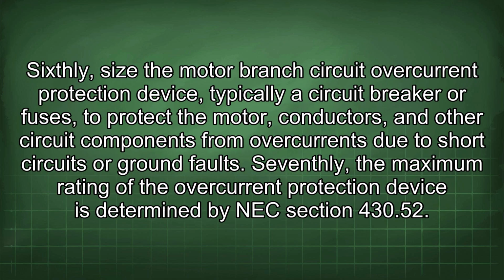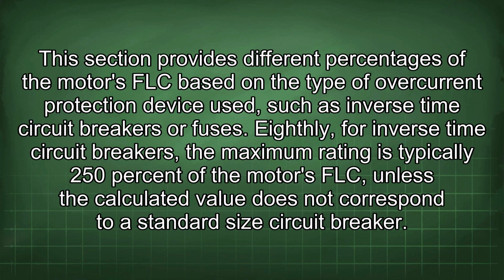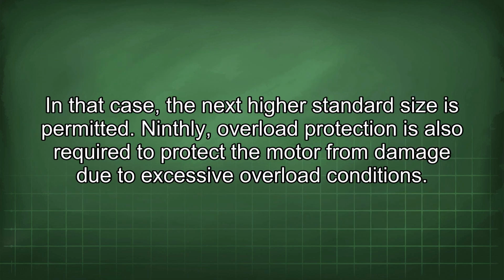Sixthly, size the motor branch circuit overcurrent protection device, typically a circuit breaker or fuses, to protect the motor, conductors, and other circuit components from overcurrents due to short circuits or ground faults. Seventhly, the maximum rating of the overcurrent protection device is determined by NEC section 430.52. This section provides different percentages of the motor's FLC based on the type of overcurrent protection device used, such as inverse time circuit breakers or fuses. Eighthly, for inverse time circuit breakers, the maximum rating is typically 250% of the motor's FLC, unless the calculated value does not correspond to a standard size circuit breaker. In that case, the next higher standard size is permitted.